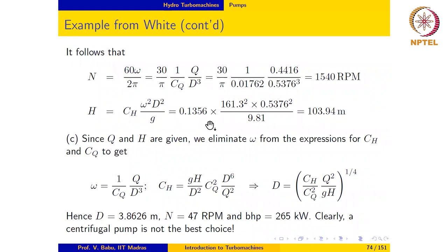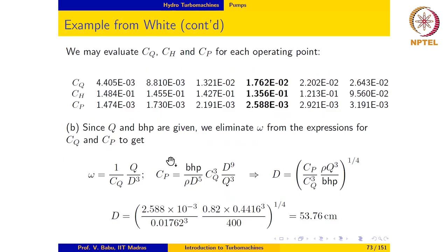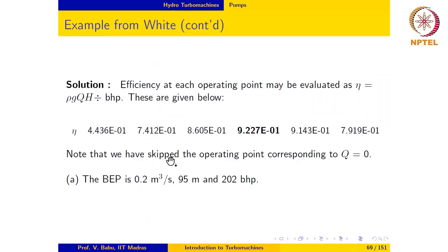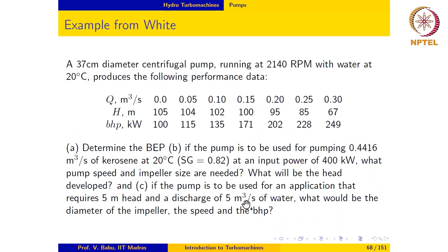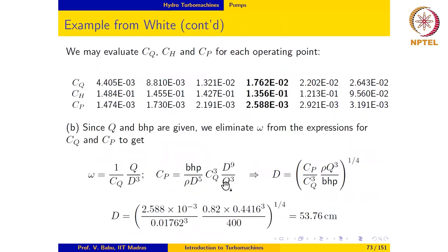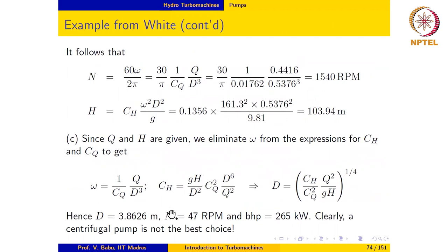Let us try and get a physical understanding of why a centrifugal pump is not a good choice for the values of Q and H that we had specified. The value of Q and H specified for this case was 5 meter head and 5 cubic meters per second of water. Looking at these values, it is apparent that the requirement calls for low head and high flow rate, and that is the reason why a centrifugal pump is not a good choice.